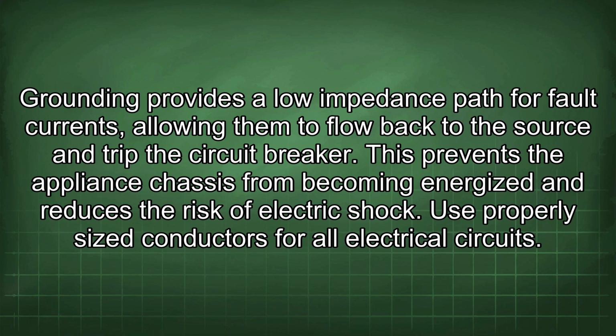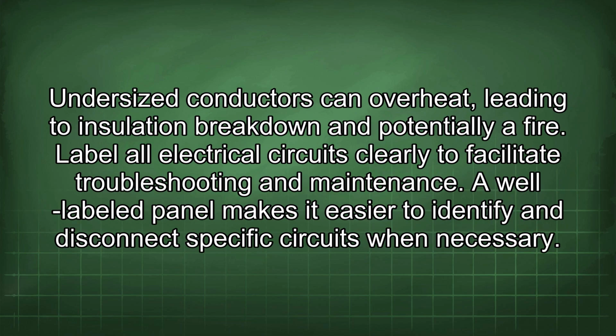Use properly sized conductors for all electrical circuits. Undersized conductors can overheat, leading to insulation breakdown and potentially a fire. Label all electrical circuits clearly to facilitate troubleshooting and maintenance. A well-labeled panel makes it easier to identify and disconnect specific circuits when necessary.